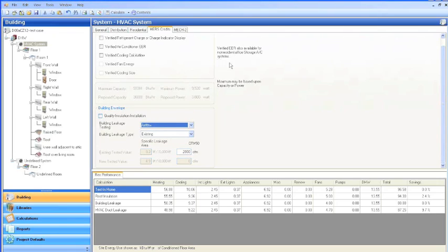If you have a Title 24 HERS rater come and inspect the installation of an air conditioner unit, which is required in all the inland climate zones, 2 and 9 through 16, whenever an air conditioner is installed by code, you're expected to have that looked at, is my understanding.